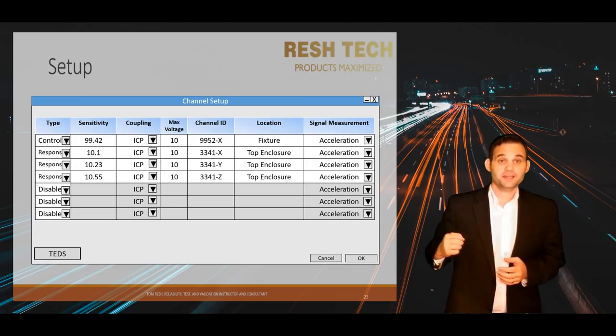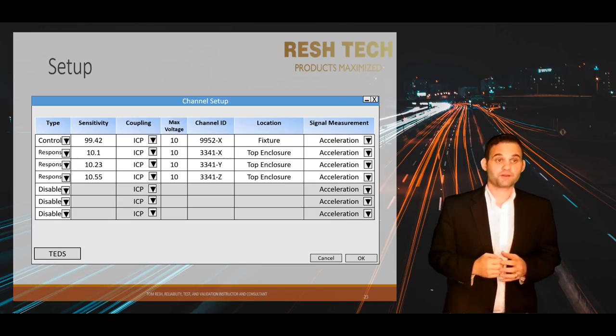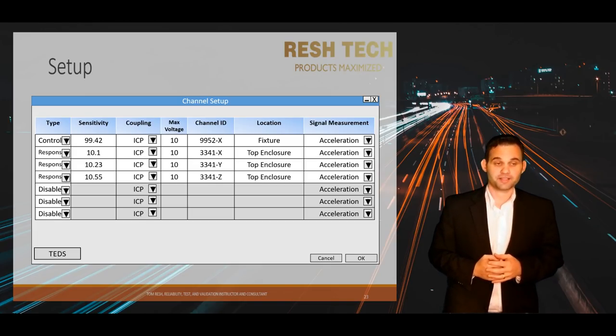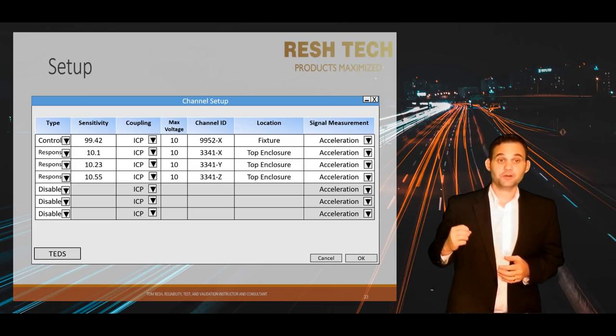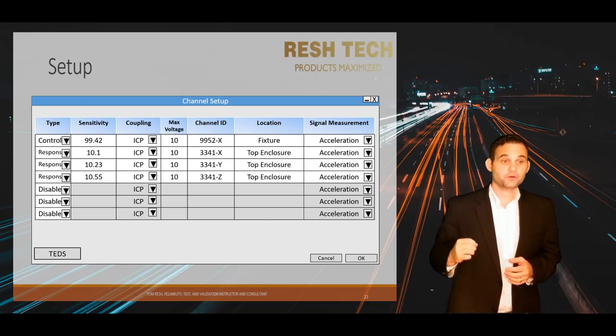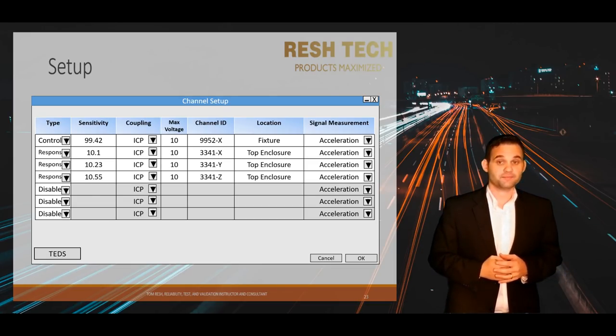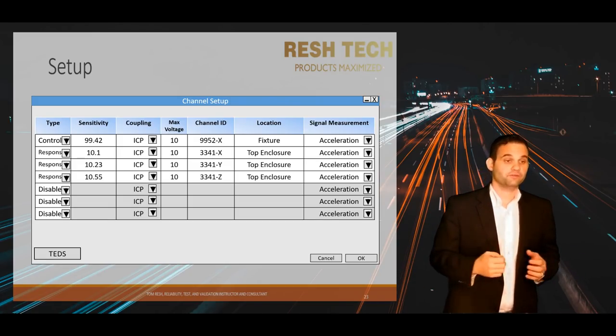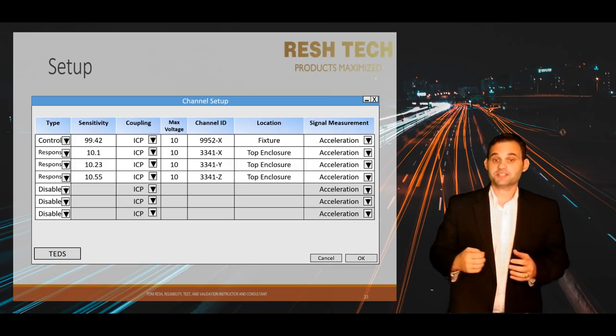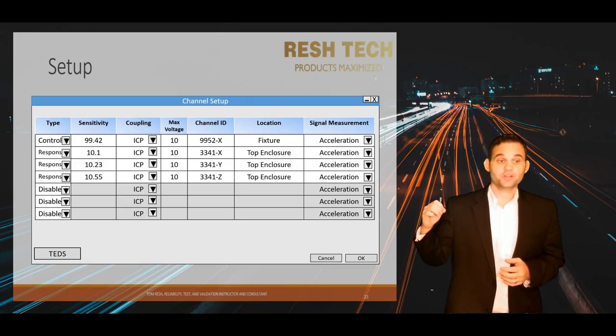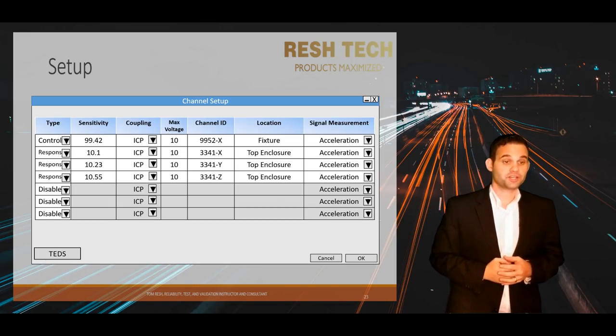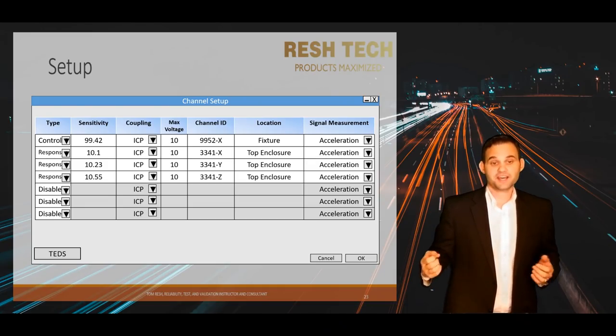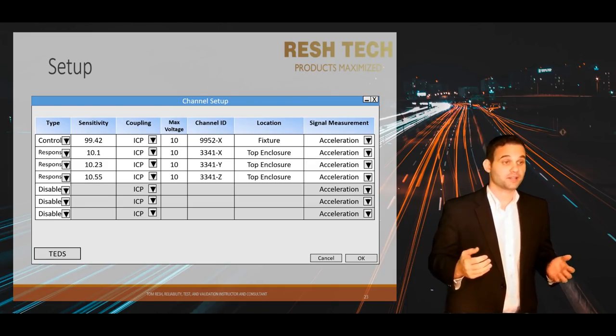The channel ID column is where my personal preference is to enter the serial number of that particular sensor and the axis it is mounted in. Next is the location ID — enter the location where your accelerometer is mounted, such as on the fixture or the top cover of your unit. The last column is the measurement type field, where you select what you are measuring, such as acceleration, velocity, or even pressure or temperature on some controllers. In this case, we are using accelerometers, so we select acceleration.